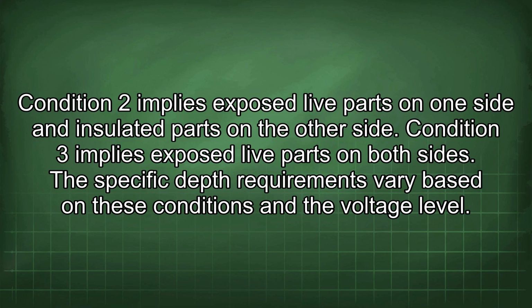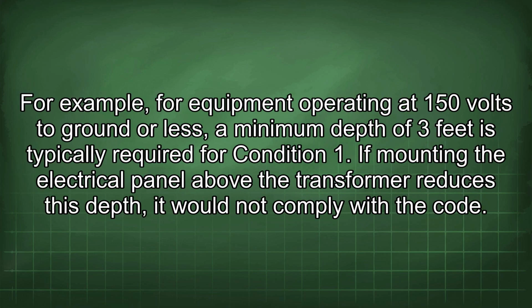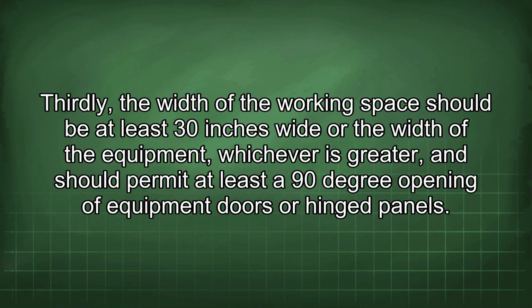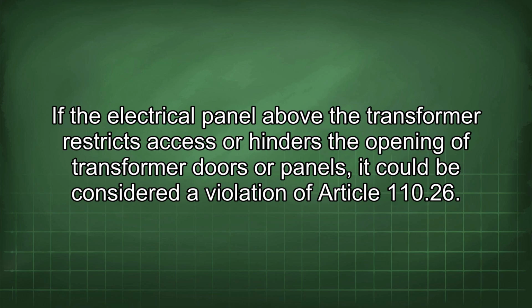The specific depth requirements vary based on these conditions and the voltage level. For example, for equipment operating at 150 volts to ground or less, a minimum depth of 3 feet is typically required for condition 1. If mounting the electrical panel above the transformer reduces this depth, it would not comply with the code. Thirdly, the width of the working space should be at least 30 inches wide, or the width of the equipment, whichever is greater, and should permit at least a 90-degree opening of equipment doors or hinged panels. If the electrical panel above the transformer restricts access or hinders the opening of transformer doors or panels, it could be considered a violation of Article 110.26.